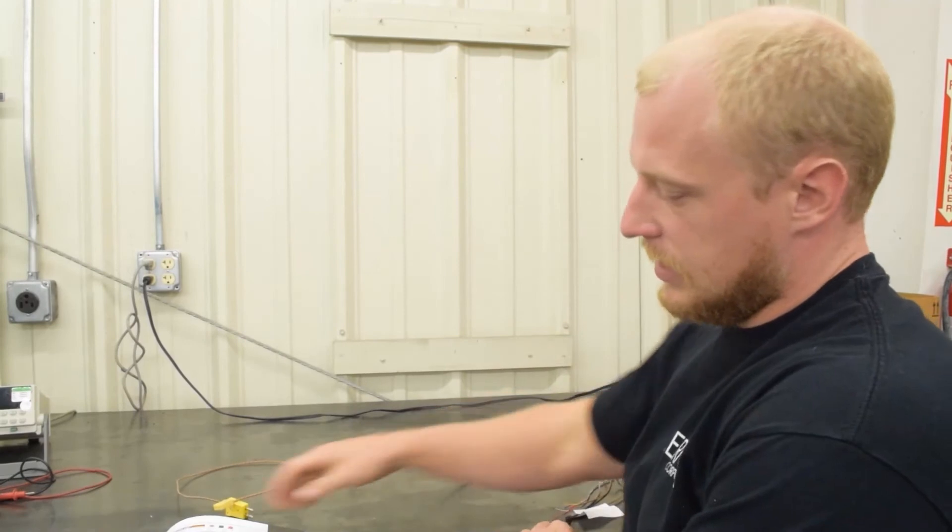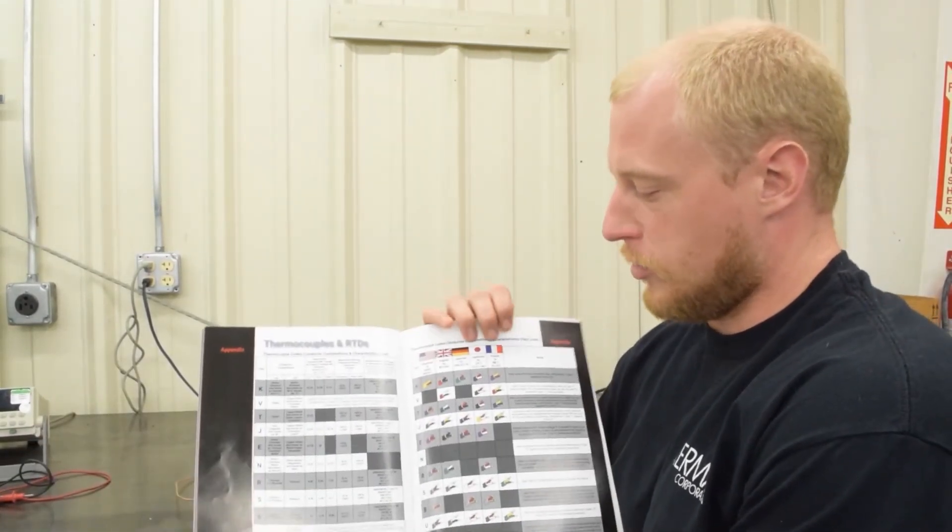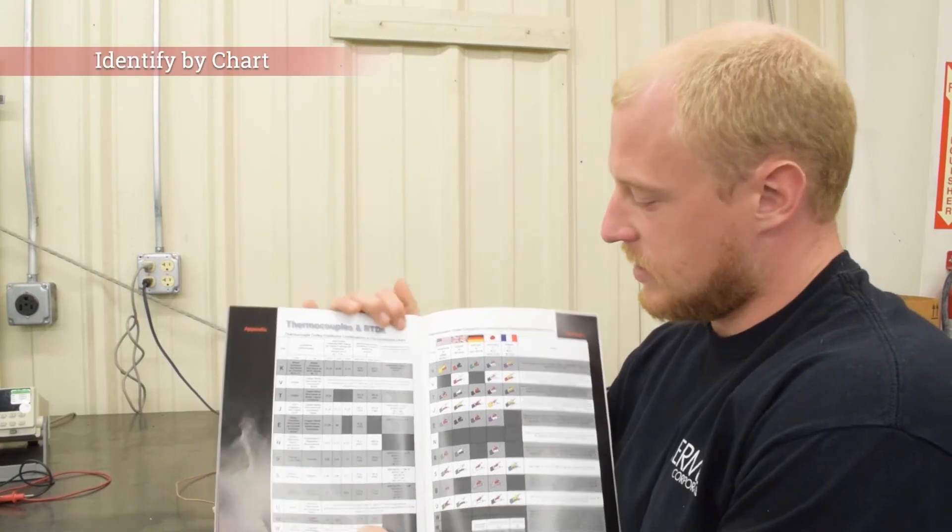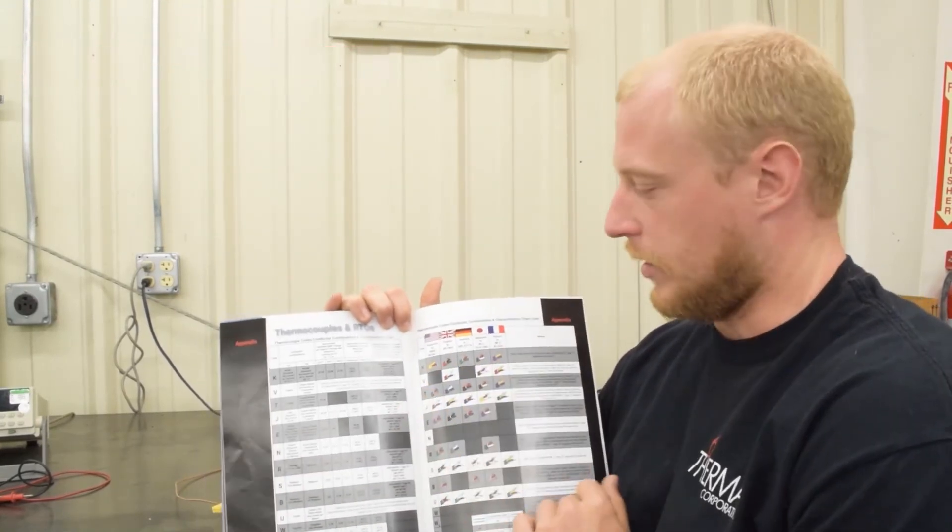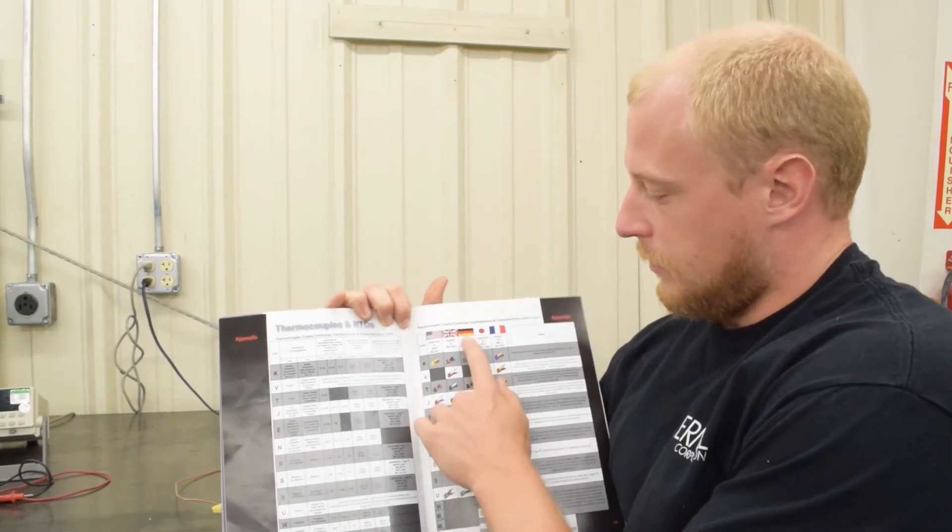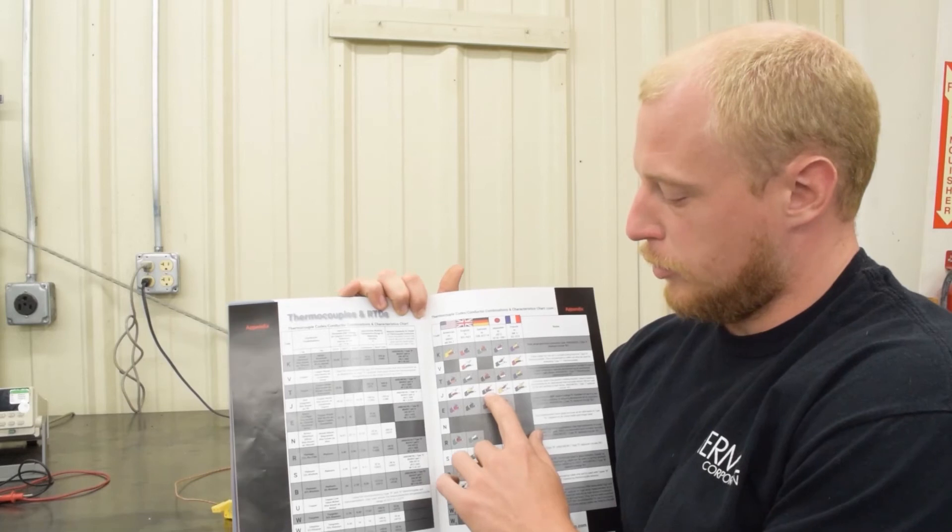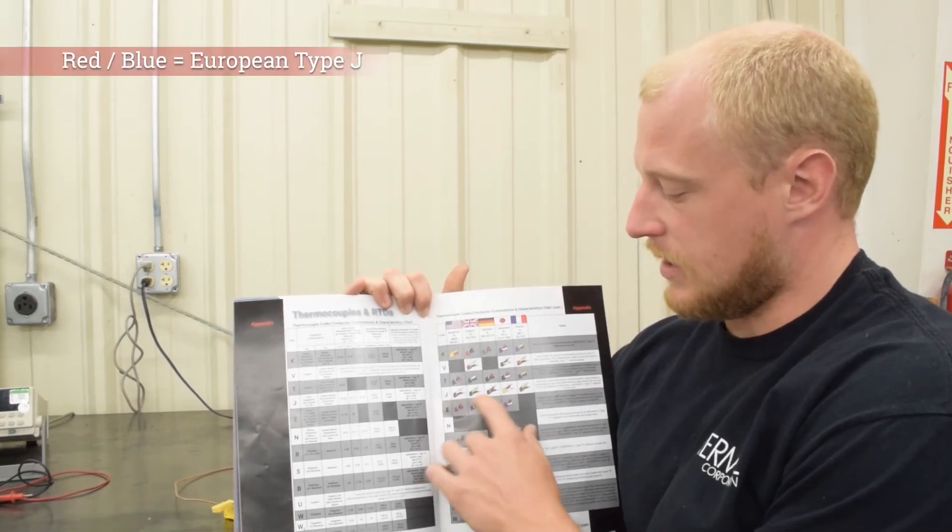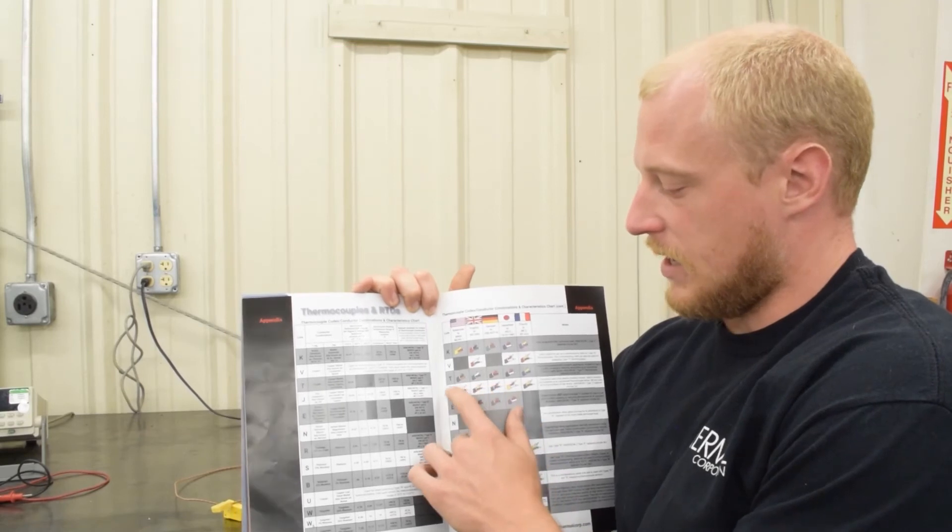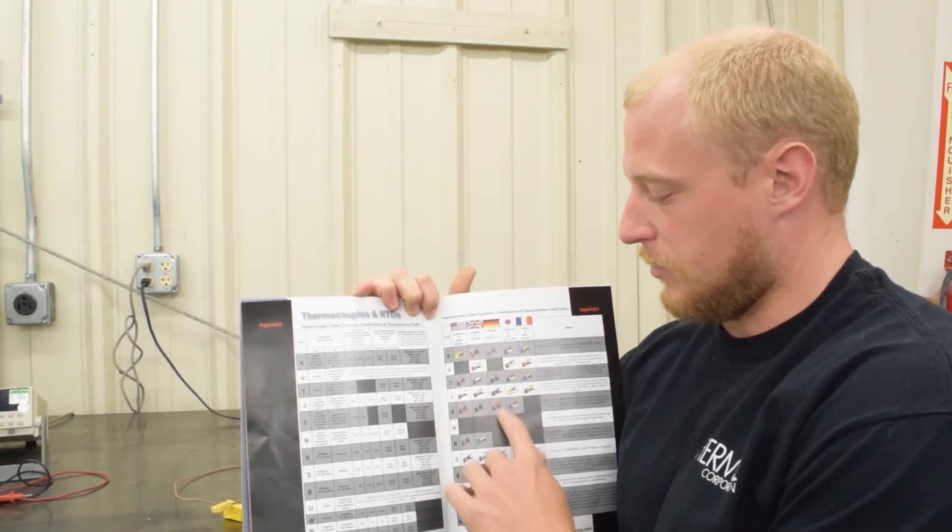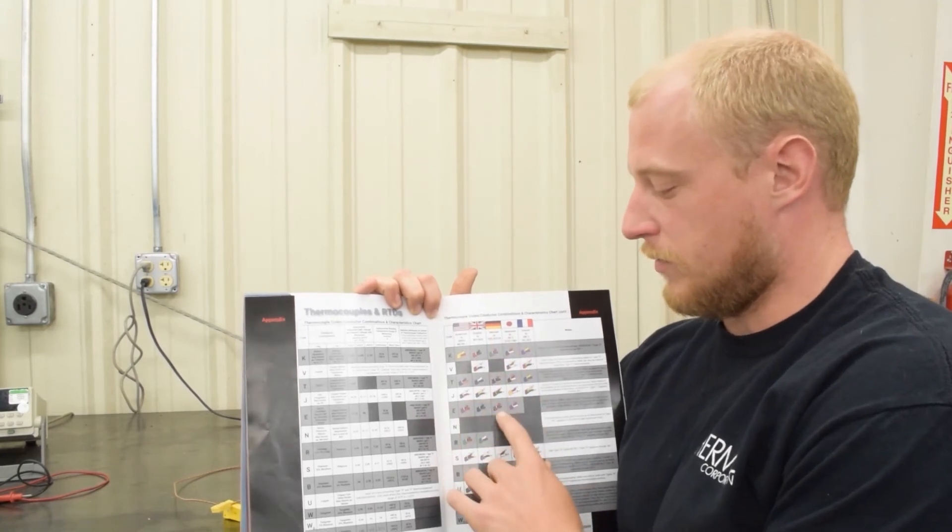We look at in our catalog we have a thermocouple and RTD chart and you can see this is in our catalog, it's on our website, it's widely available online, but in Europe for German a red and blue lead thermocouple is actually a type J thermocouple and so this is a type J thermocouple but that machine was most likely produced in Europe and so it conforms to a different color code.